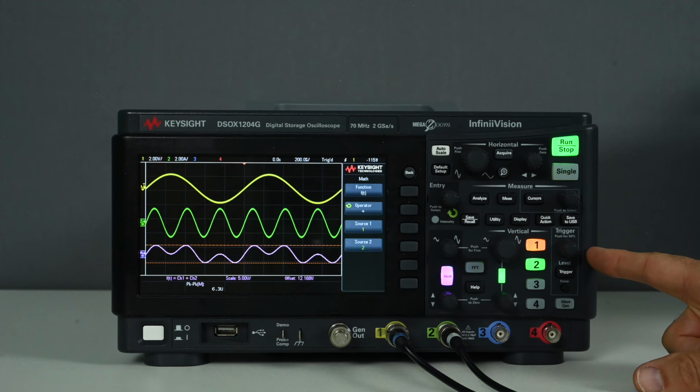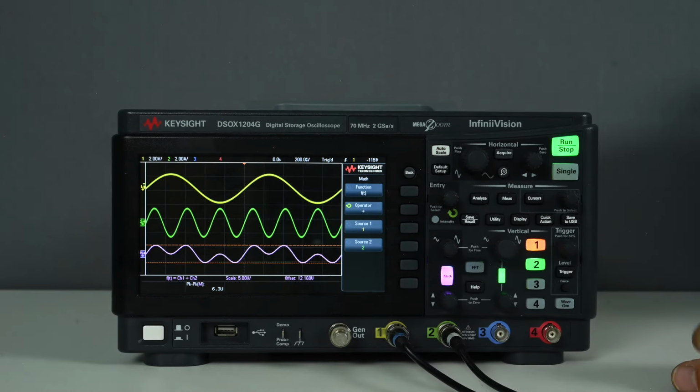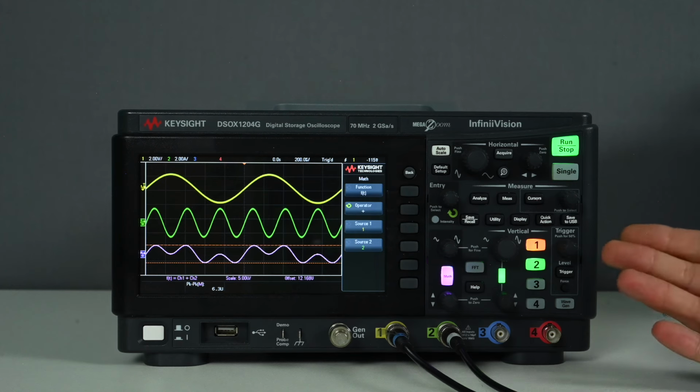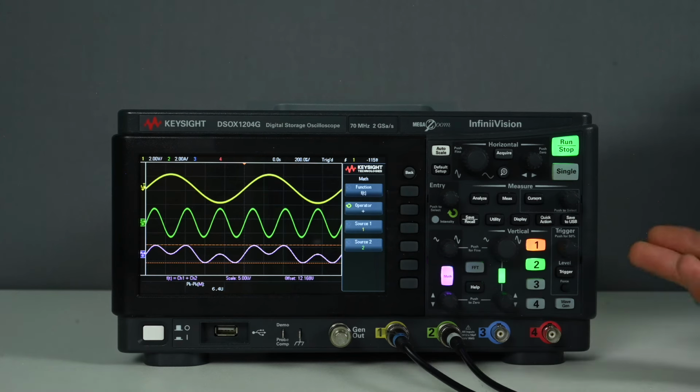On the Rohde & Schwarz, we always have to set our unit ourselves. It does not automatically take a unit, but the Keysight and the Siglent, even in a more advanced way, choose your unit. So it can also be voltage squared or whatever the result of your calculation is.